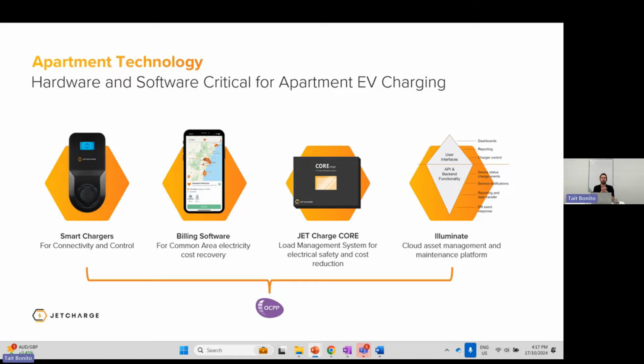Another critical technology, especially for retrofitting in apartment settings, is the JetCharge Core load management system. This is critical for enabling scalable EV charging in apartments, because a single EV charger can draw as much power as an entire apartment unit. If you're installing 10, 20, 30 chargers into a building, you'll quickly run into constraints on spare electrical capacity.